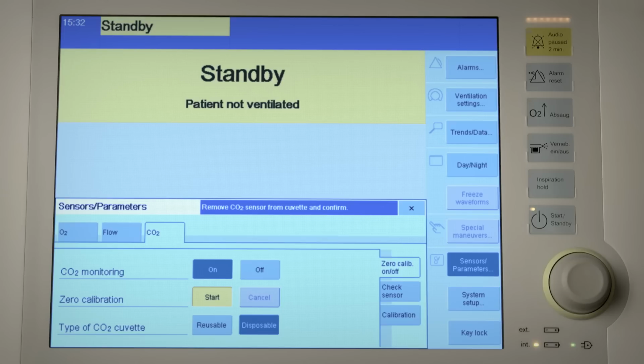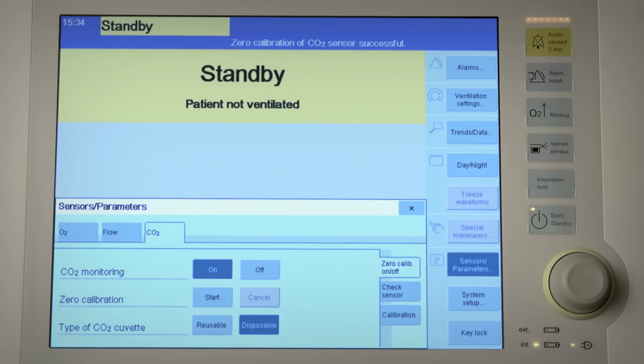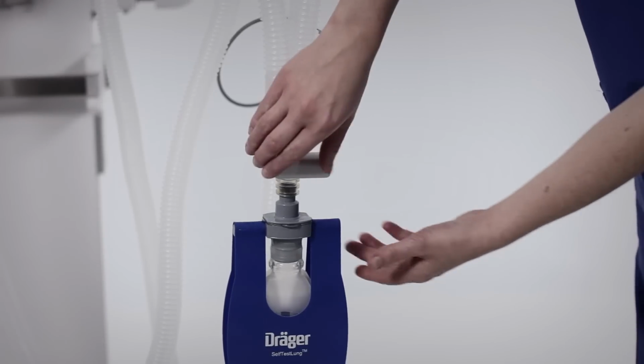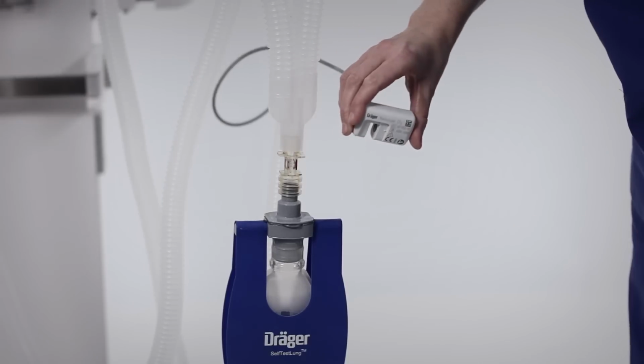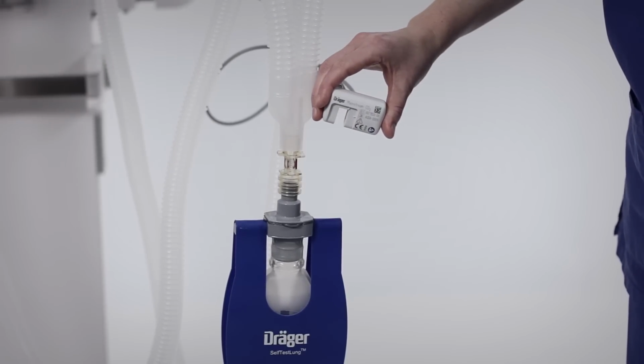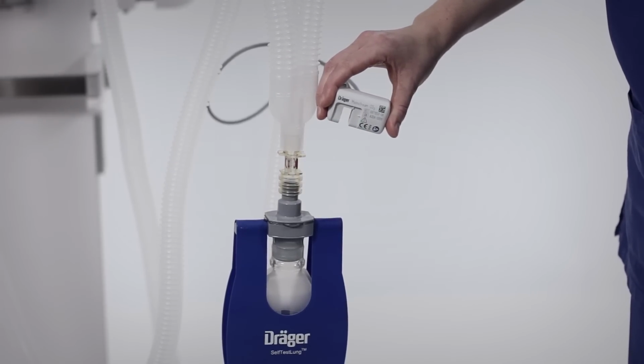If CO2 monitoring is used, check the CO2 zero indication. The prerequisite for that is a clean CO2 sensor placed on the cuvette. Use a clean or a new cuvette. At least a 3-minute warm-up phase for the CO2 sensor must have elapsed. Select the cuvette type and display CO2 measured values as a curve in the Configuring Curve field. Remove the CO2 sensor from the cuvette and hold in ambient air. Do not breathe on or into the cuvette.